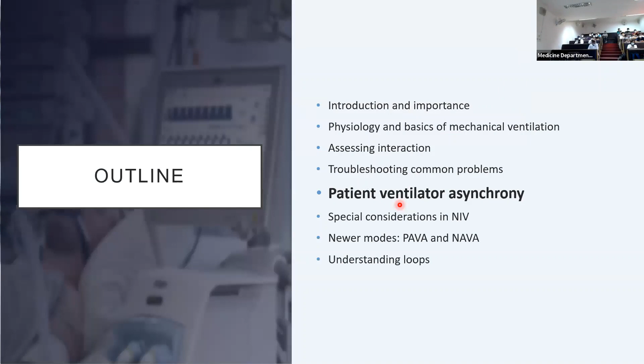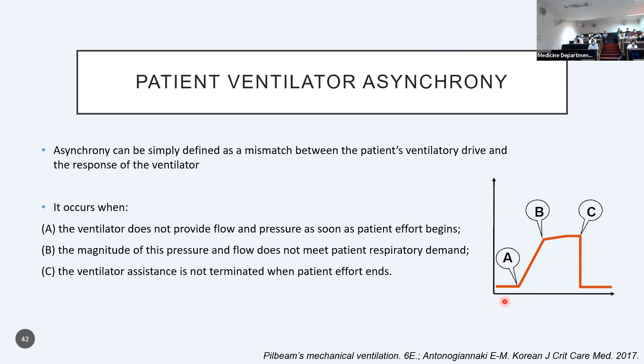or when he's taking the flow, the ventilator is not providing him adequate flow, which is flow asynchrony, or when he wants to expire, but the ventilator is either delaying expiration or prematurely letting the patient expire. So these are the three main areas where asynchrony may happen: during triggering, during the flow, or during cycling, when there's mismatch between the patient's response and the ventilator.